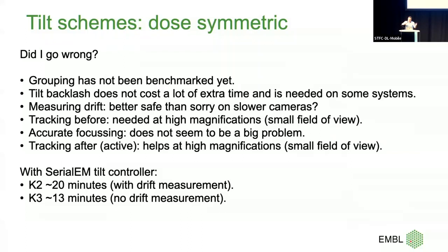Tracking at higher magnifications: you really need to track, or we should get larger cameras or a better stage — the root cause is we have a bad stage and can't just tilt and shoot. Accurate focusing: I think I have to drop that now, or at least benchmark it first. It's always difficult to take something out without controlling everything — if the sample was bad I'd be blamed. Active tracking after: taking a trial image after your record image before tilting helped a lot. With SerialEM, tilt series on K2 are now about 20–25 minutes, and on K3 about 13 minutes.